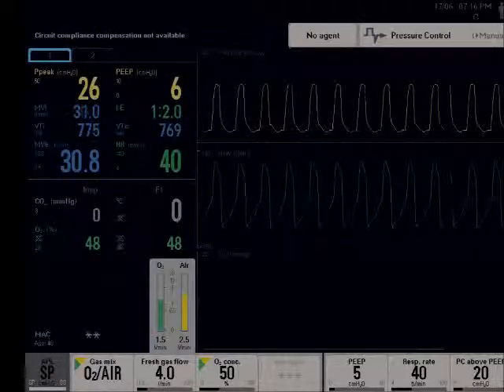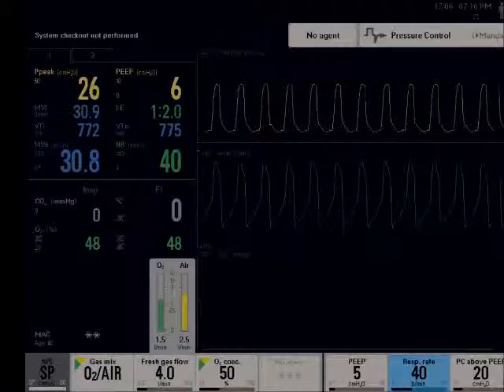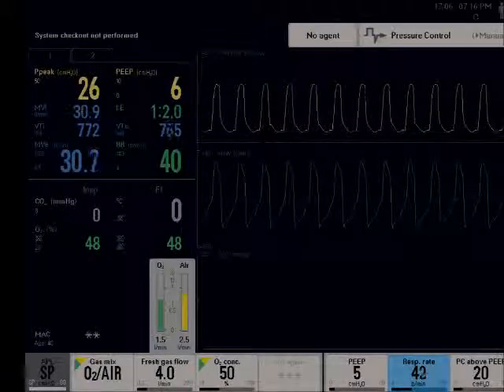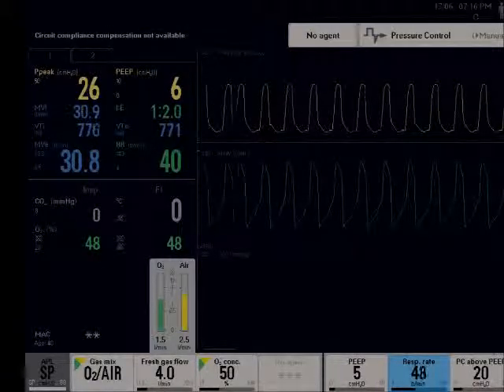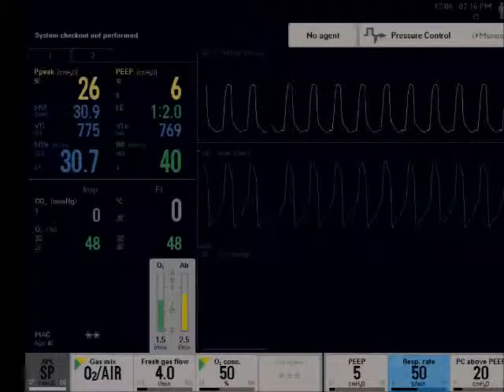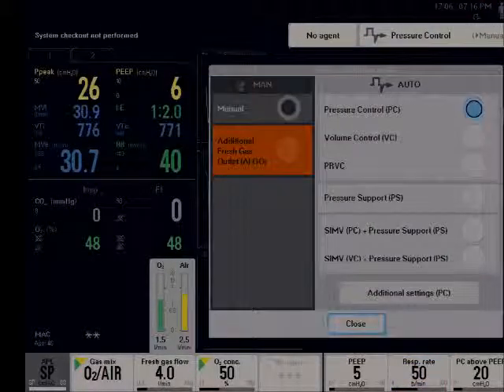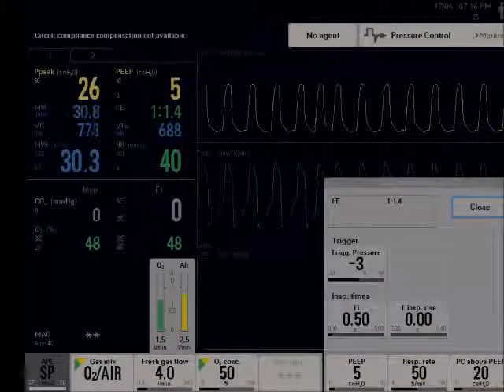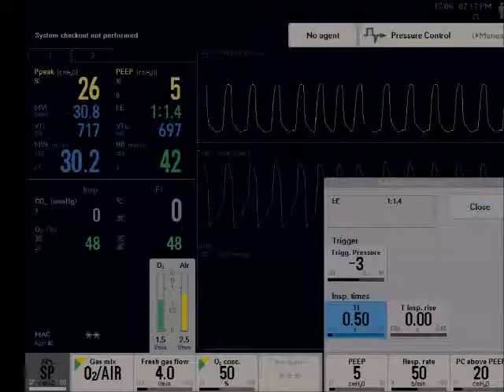I'm going to increase my respiratory rate again. Let's change it to 50 and see what happens. So I'm going to increase it to 50. I'm going to go to my additional settings, change my inspiratory time percent, and keep an IE ratio of 1 to 2.